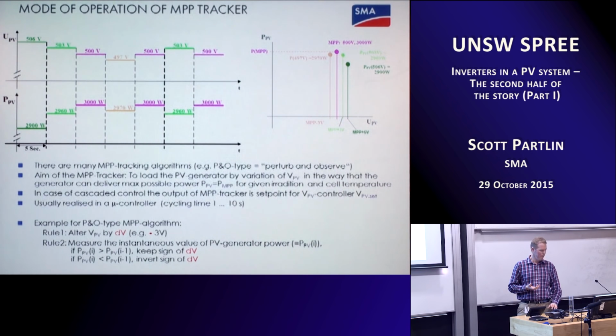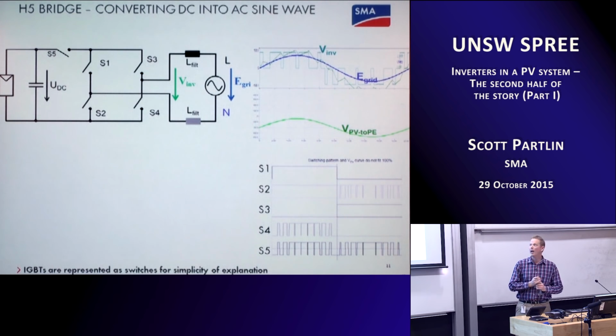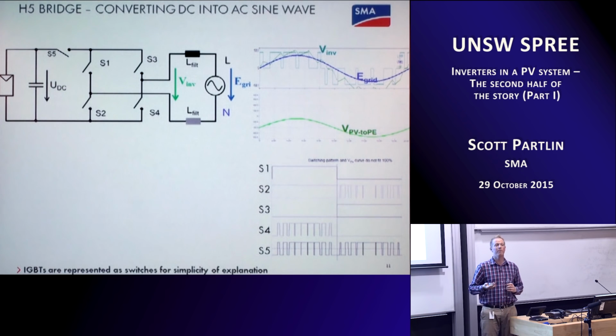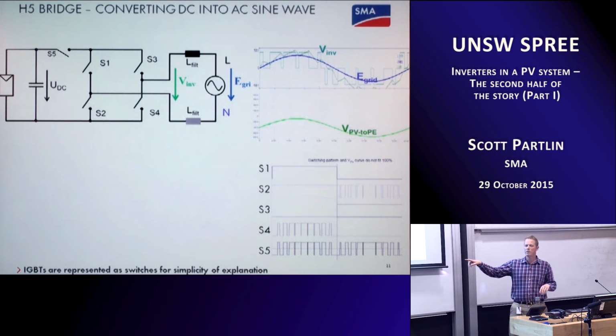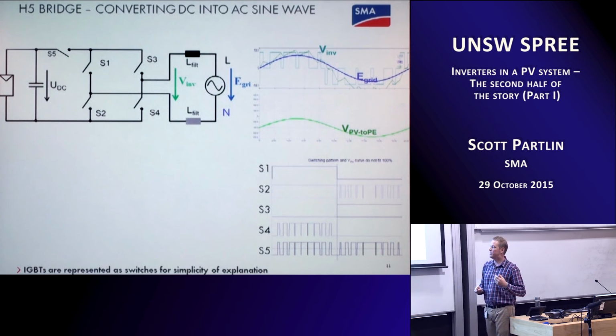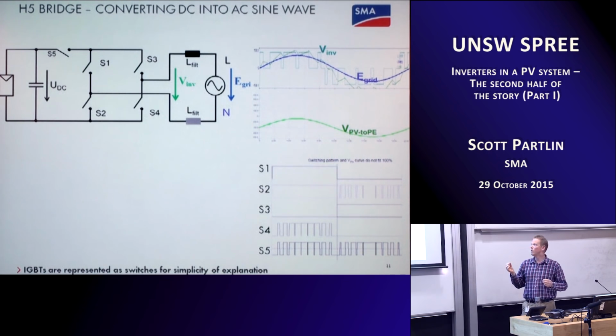The other part of an inverter is converting the DC into AC. So what I've got here is a very simplified circuit diagram of a single phase transformerless inverter with an H5 bridge. Each of these switches is an IGBT, an insulated gate bipolar transistor, essentially just a switch. I've represented them as switches to show how we take a DC that might be at, say, 500 volts plus, and turn it into our 240 volts or 230 volts RMS AC output wave.